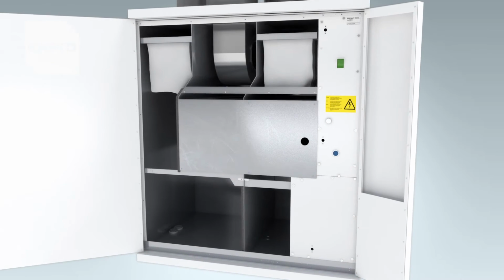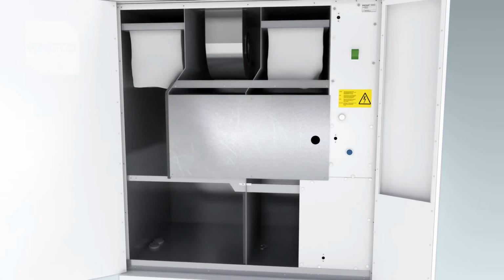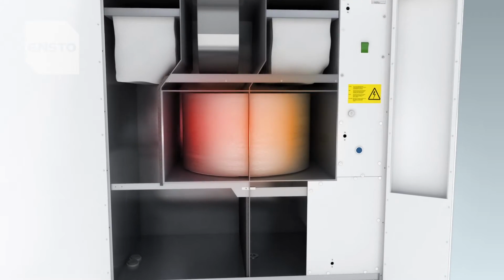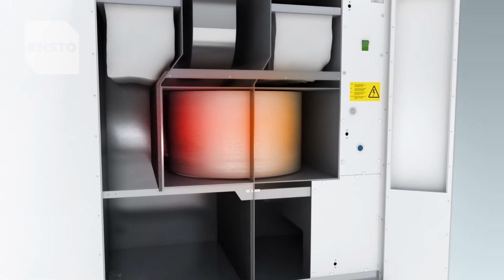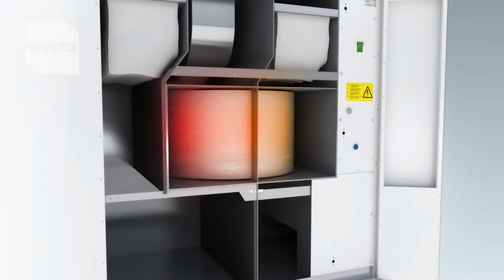The rotating heat exchanger is a regenerative, heat-storing unit at the heart of the home, ensuring energy savings for the whole building. The rotating heat exchanger consists of a round cell-type disc, rotating slowly between the supply and exhaust air. The cells of the heat exchanger store heat from the extract air, which is transferred back into the supply air by the rotation of the heat exchanger cells. The air currents flow in the opposite direction from the cells.